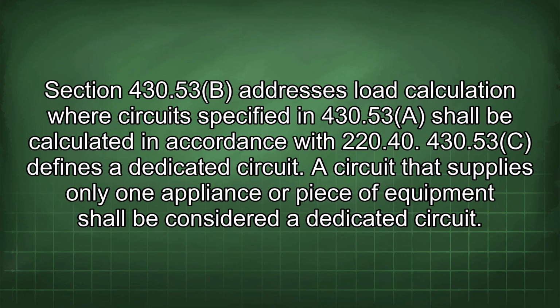Section 430.53(B) addresses load calculation, where circuits specified in 430.53(A) shall be calculated in accordance with 220.40. 430.53(C) defines a dedicated circuit. A circuit that supplies only one appliance or piece of equipment shall be considered a dedicated circuit.